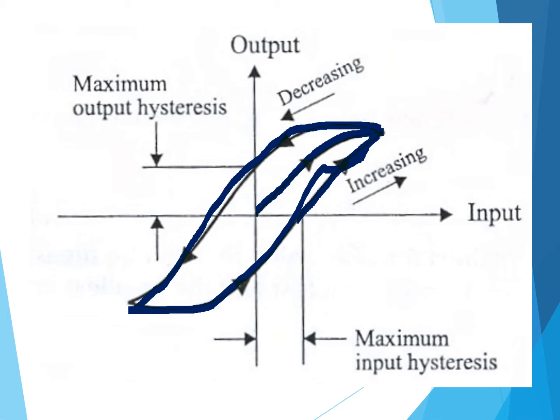When x is 0 and y has some value on the descending curve, that gives the maximum output hysteresis. When the output y-axis is 0 and there is some input value on the scale, the difference gives the maximum input hysteresis.